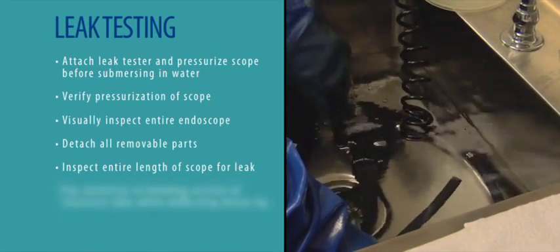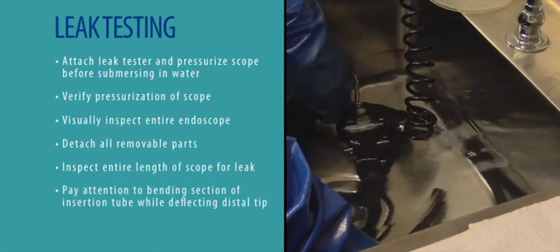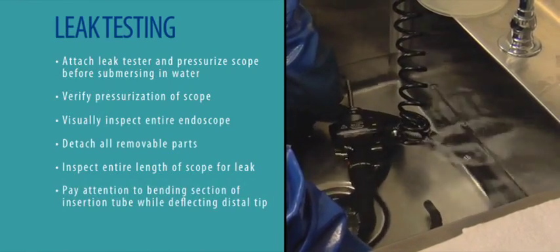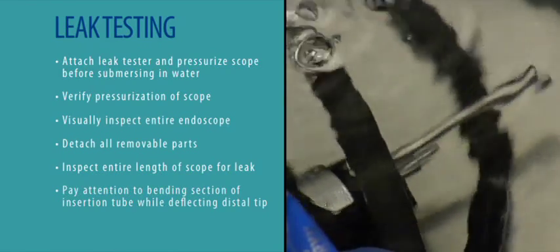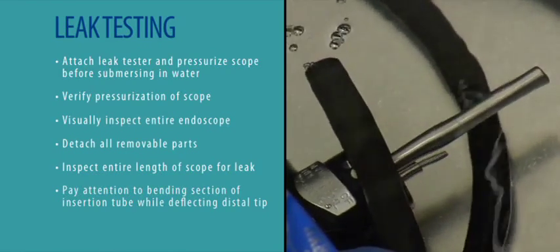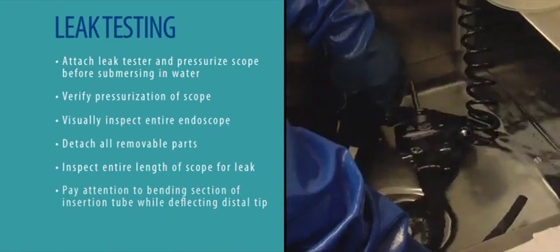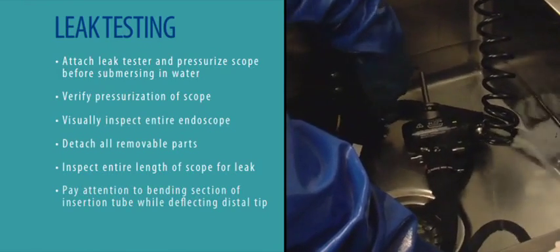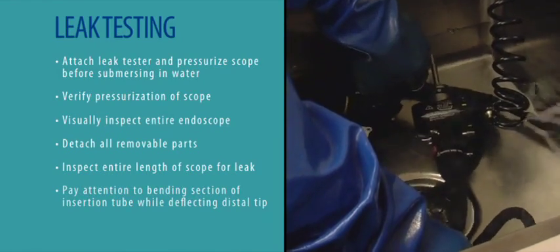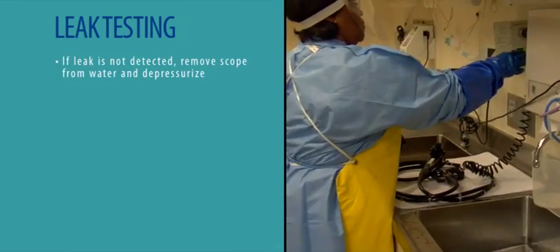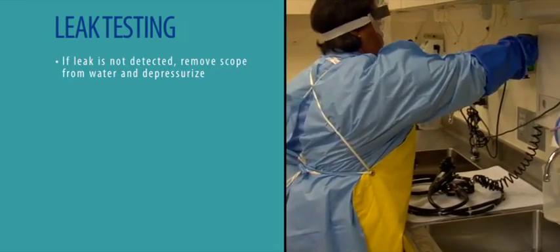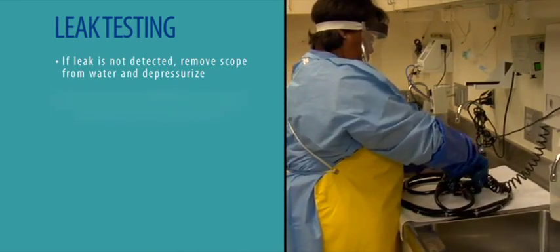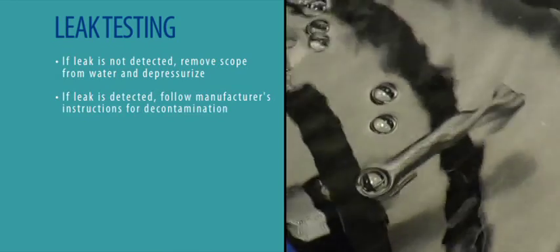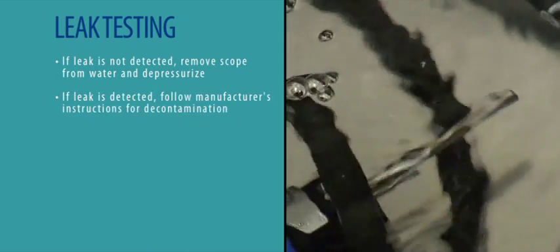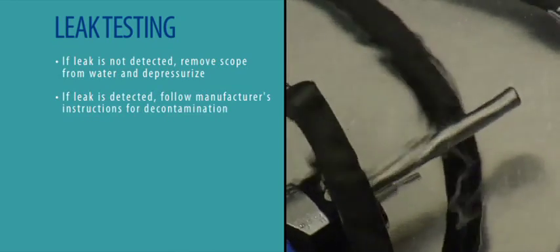Pay particular attention to the bending section of the insertion tube while deflecting the distal tip in all directions. Observe for bubbles coming from control knobs, the insertion tube, and the openings of the internal channel at the distal tip, the valve ports, and the connectors. If a leak is not detected, remove the scope from the water and depressurize the scope. If a leak is detected, follow manufacturer's instructions for decontamination to avoid further damage.